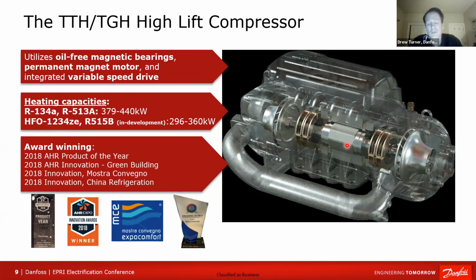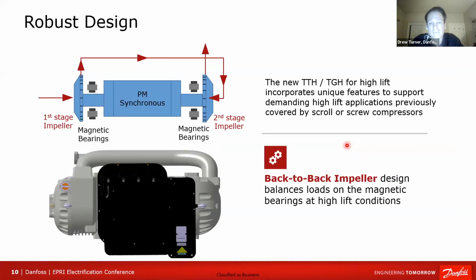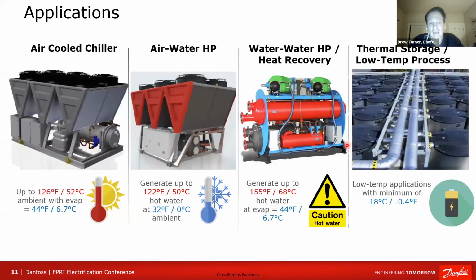And so what you can do to help balance those forces is change the mechanical design. What we did is we took that second stage of compression and moved it down to the opposite end of the compressor, so that those axial forces on those bearings are pulling back against each other, which helps enable that capability. And this illustrates that. This is the new latest design. And what that enables is, if you're doing an air-cooled chiller in Dubai, we can do that now. We didn't used to have that capability.